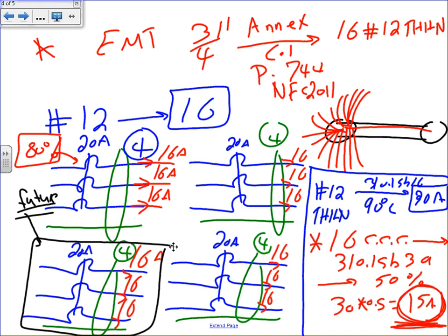Everybody can see that I have 12 in the whole system. I have 12 20-amp branch circuits. What does that mean? These are 1, 2, 3, 4, 5, 6, 7, 8, 9, 10, 11, 12. I can put more than two-thirds of this panel in 3/4 of an inch. That's powerful. Does that make sense? Just to give the gravity of what we're trying to do. When you put 12 of these branch circuits, all the conductors that come out of them, in 3/4 of an inch, I think that's powerful. So keep this in mind. I'm going to summarize here, just to put right somewhere here, that we have 12 in this system.